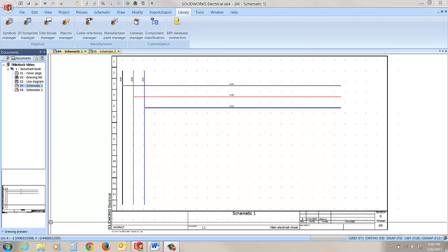In this video, I'm going to share some tips to help you develop a title block in SOLIDWORKS Electrical with rows and columns. In electrical design, it is often practiced to add page or row information to wire labels. This information is used by electrical technicians during assembly or troubleshooting to trace wires back to their origin within the schematics. I'm going to show you a few tips on adding rows to your title blocks so that this information can be automatically captured onto your wire labels.